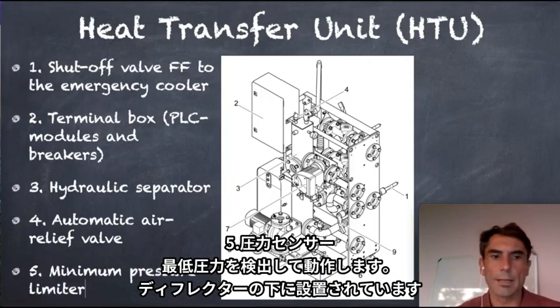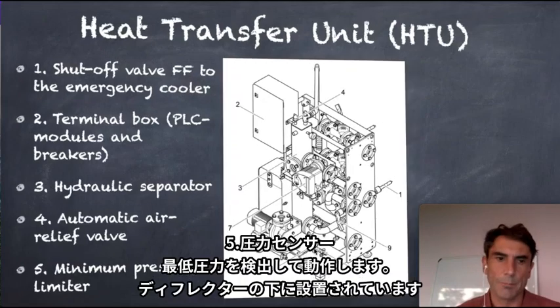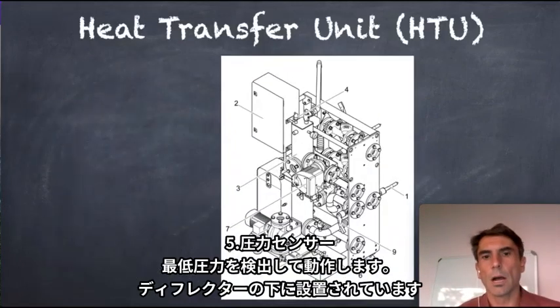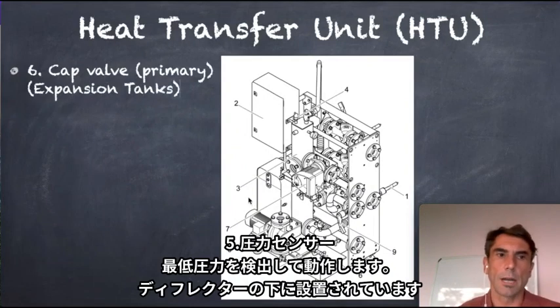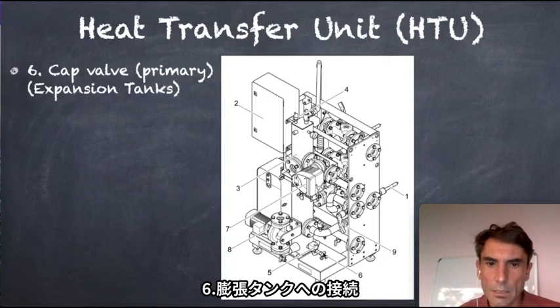And then we have number five. You see on the bottom, we spoke already of it. It's a minimum pressure limiter, so it's on low pressure. Temperature switches are always on over temperature, and the pressure here is on under pressure or low pressure. Then we have here the cap valve for the primary expansion tank. So the expansion tank will later be connected directly here at number 6.